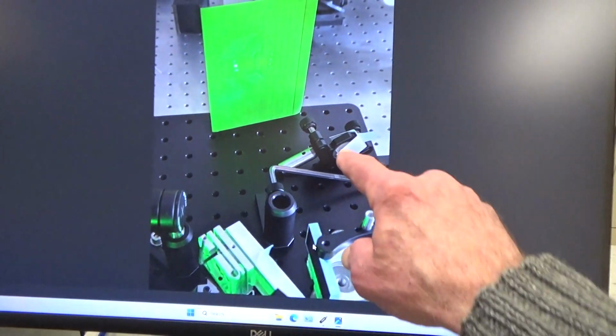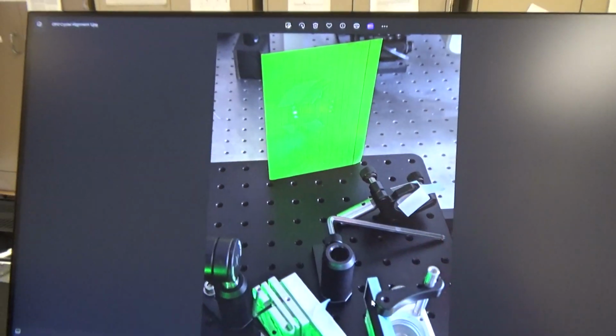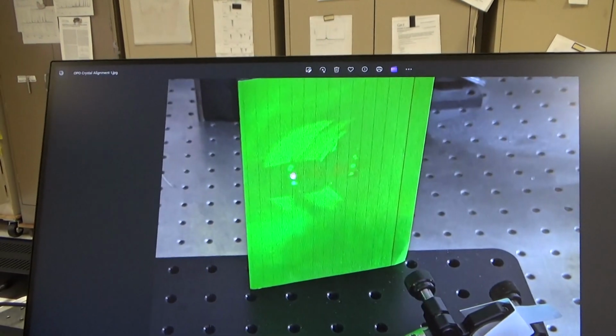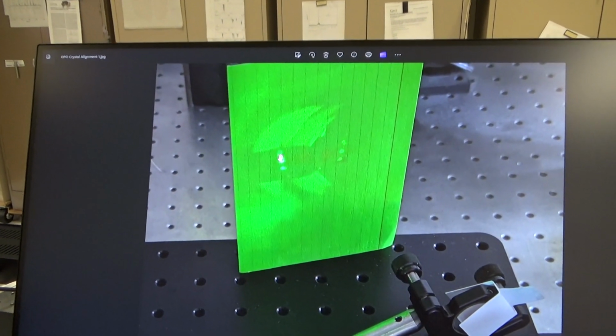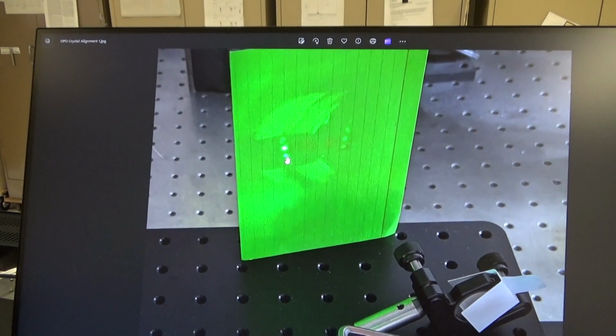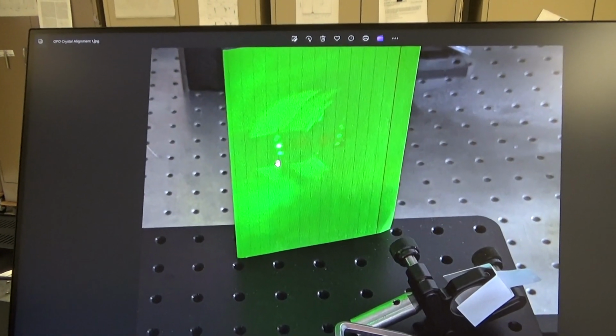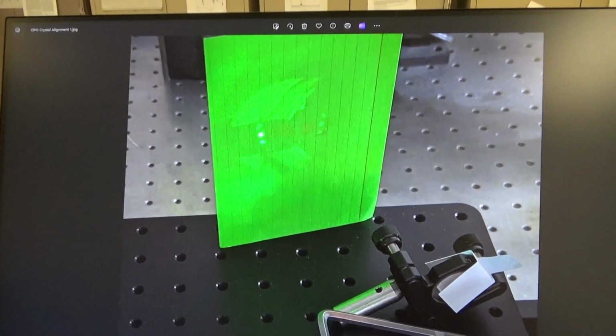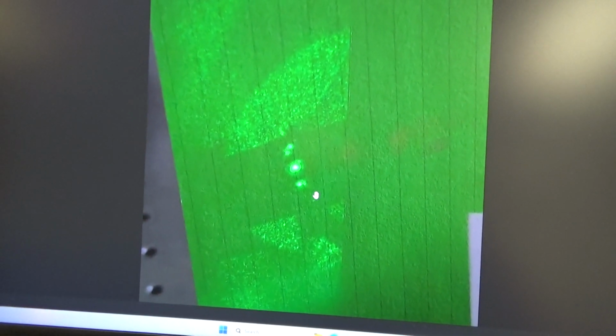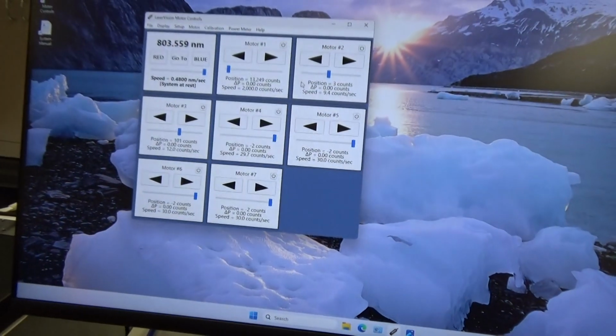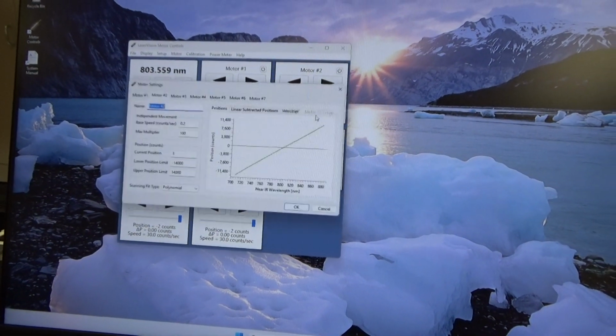So I've got the mount off to the side. Right here we can see the main beam is the brightest spot, and then there's 2 spots above and 2 spots below. Each crystal has 2 spots, one above and one below, and these rotate in opposite directions as you tune the crystals. When these spots are all in vertical alignment, the crystals are at normal incidence, and you'd want to go in and set the positions to 0.